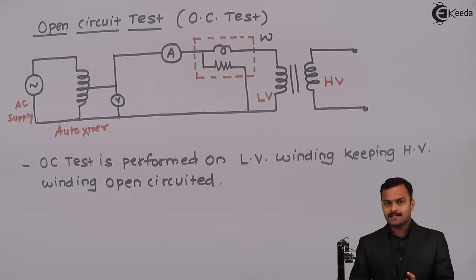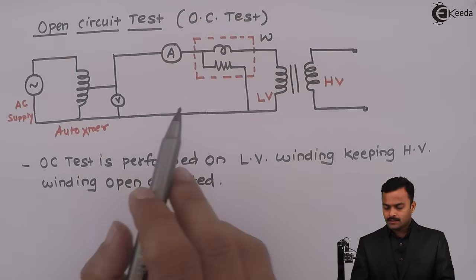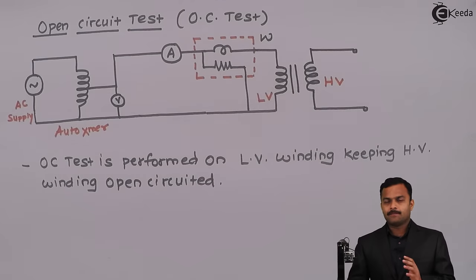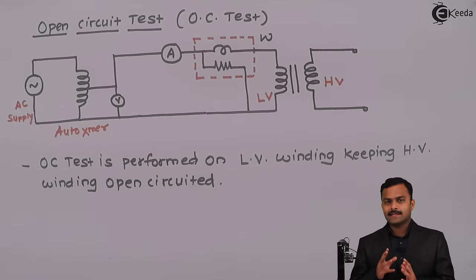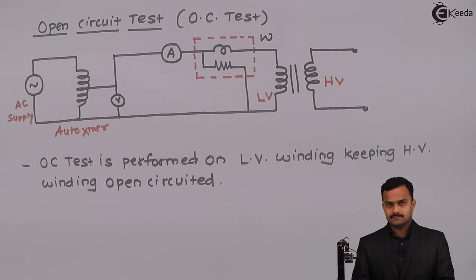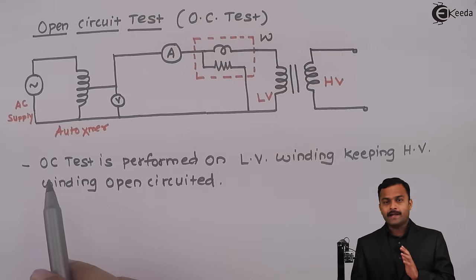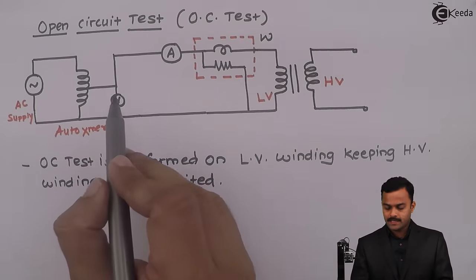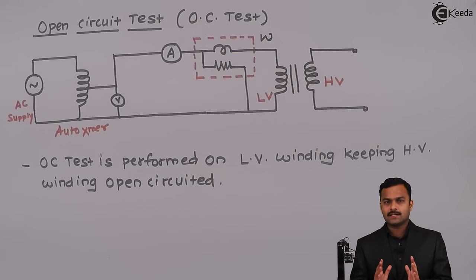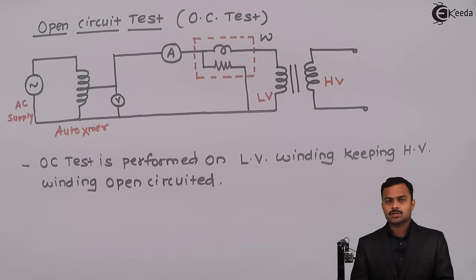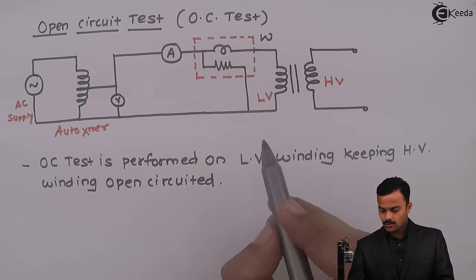If the kVA rating of a transformer is the same on primary and secondary, you get very little current when applying voltage to the high voltage side. For example, if kVA is 1 kVA, low voltage side is 100 V, and high voltage side is 10,000 V, then on the high voltage side you get a very small current that cannot be measured by the ammeter. Also, a very high voltage would be applied which the voltmeter cannot measure, so because of these meter restrictions we perform the open circuit test on the low voltage winding.